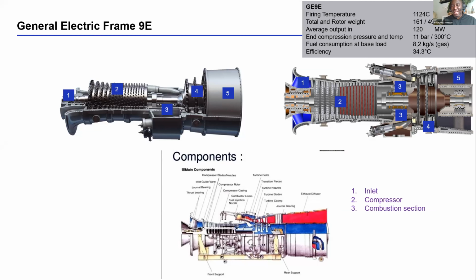So that is why it's very, very important to also check the condition of the air coming into the gas turbine. I will explain in a later stage when I talk about the different upgrades. So when they do upgrades, some customers or some countries need more power, or some need more efficiency, or some need, because of environmental conditions, less NOx, CO sent out to the atmosphere. So in this stage, they consider all this. So if you need more power, for instance, you will look for a way of increasing this temperature.